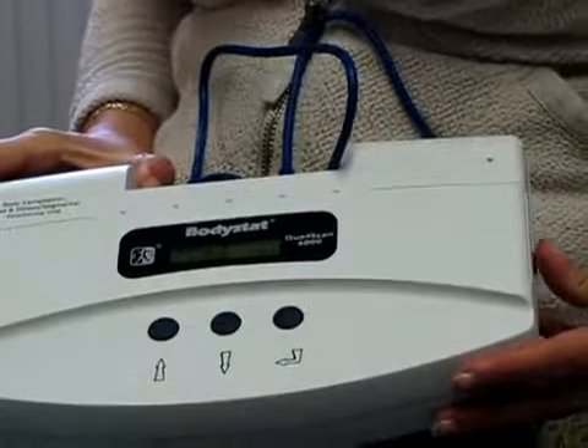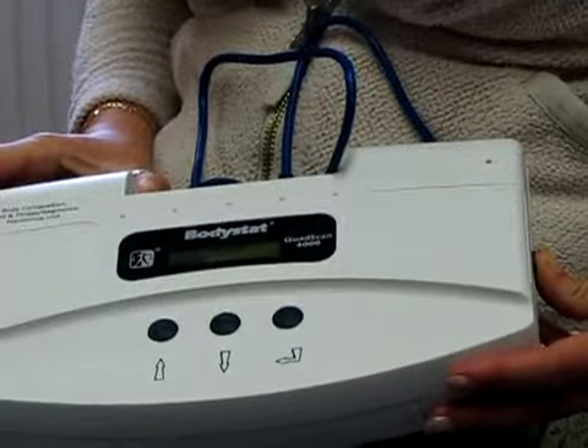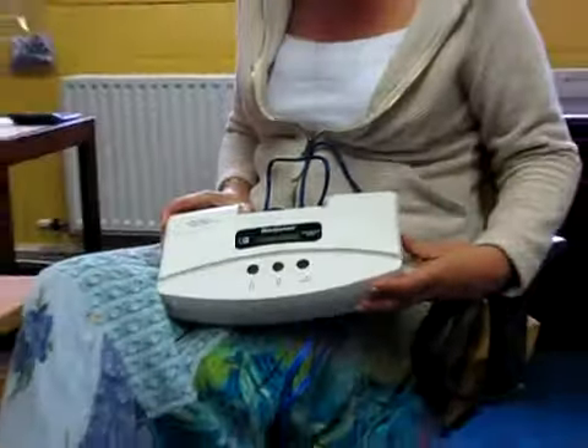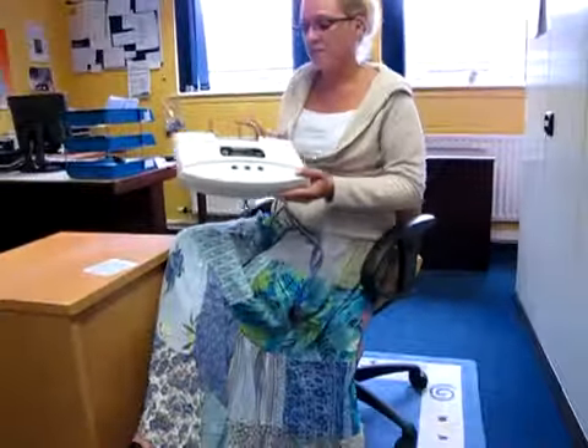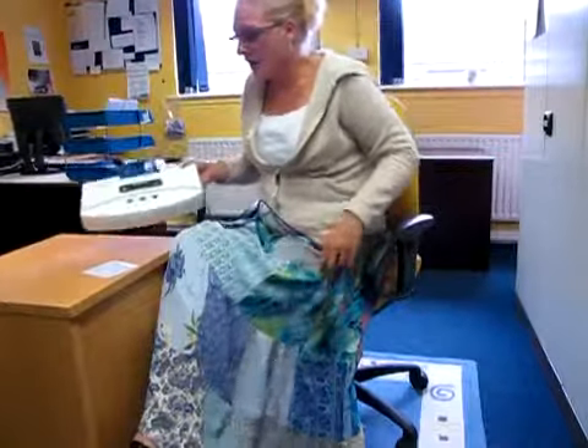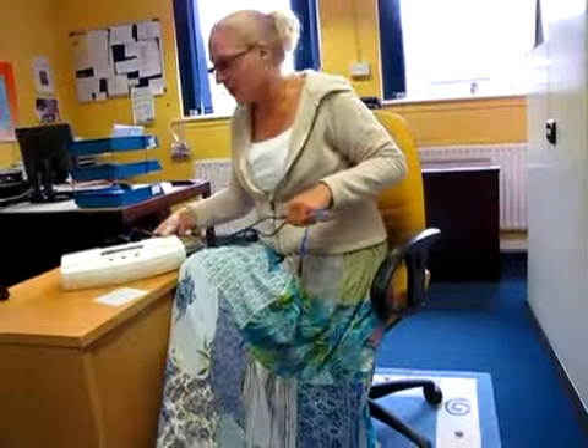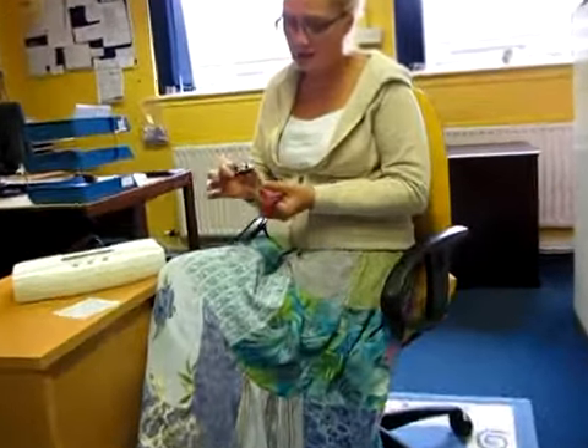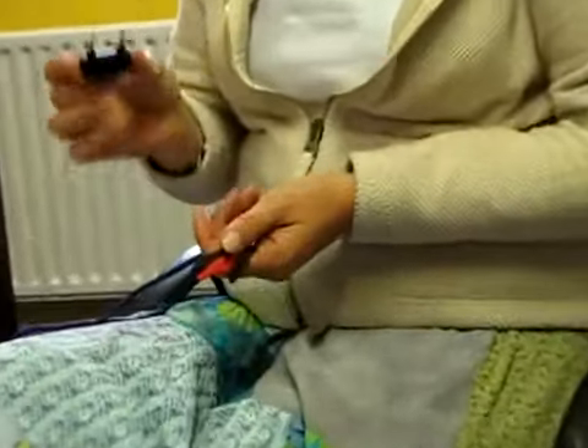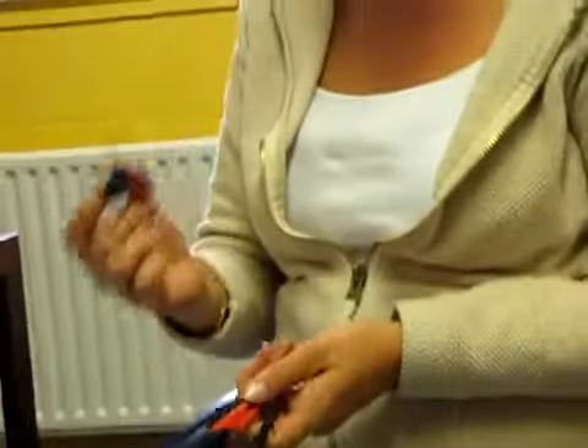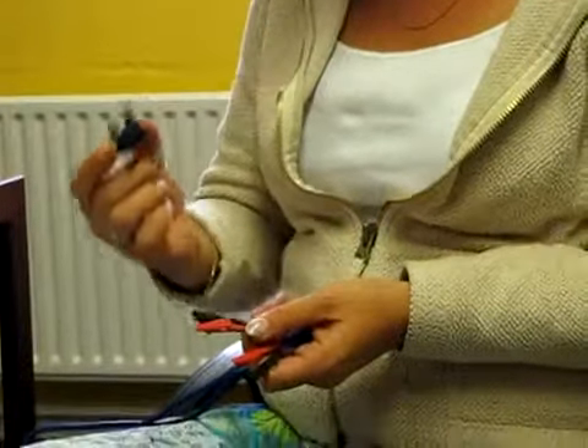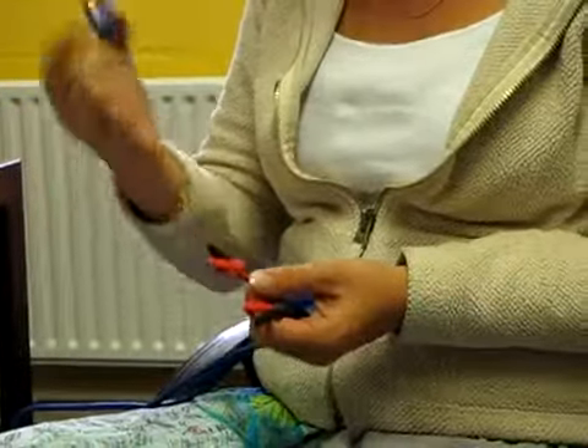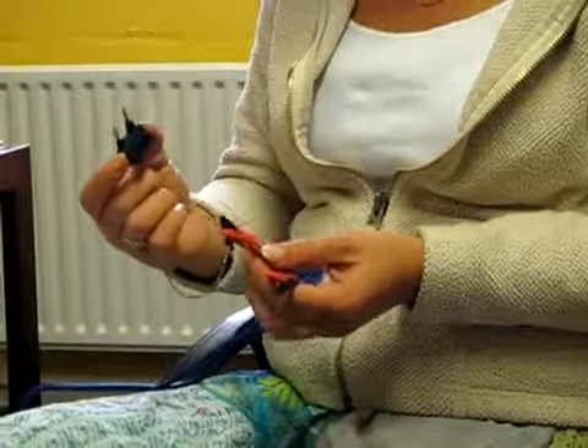If you are using the device for research, we recommend that, so you have consistency in the samples that you do, you check the devices are within calibration on a regular basis. Provided with your Quadscan pack is this calibrator. It's important to note that this does not calibrate the device itself, but it does tell you whether or not the device is still within calibration.